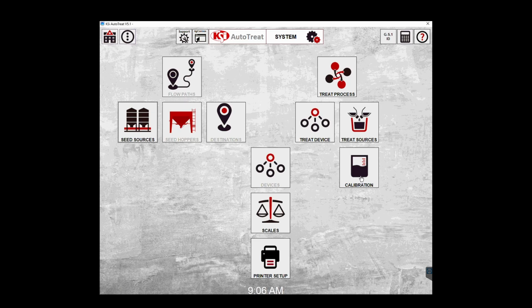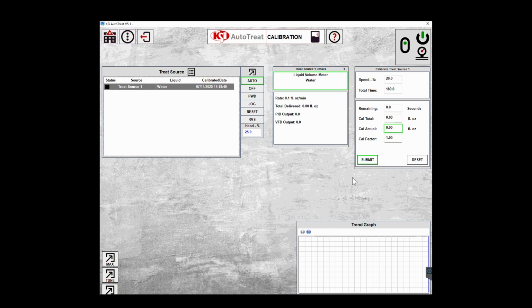For treat sources equipped with a flow meter, calibration is recommended twice daily and any time a new slurry or liquid is introduced. Treat sources using a loss in weight scale should be calibrated whenever the liquid product is changed, as the product's density is determined during initial setup.